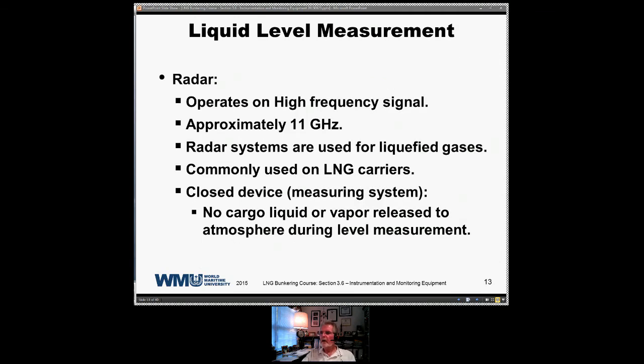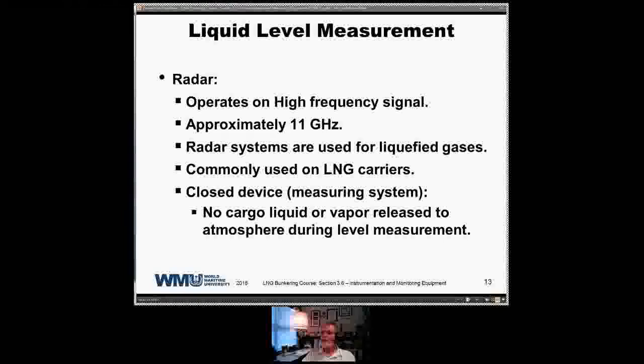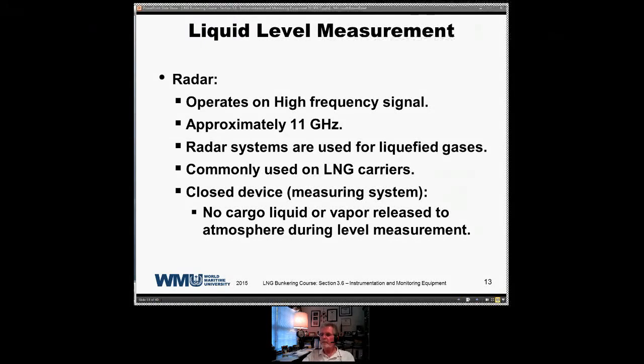Radar has been around for a long time. Now it's used to measure liquid levels on all sorts of liquid carriers. For LNG, it's a very, very popular means of measuring liquid depth inside a tank. It operates on a high frequency, 11 gigahertz, and it's obviously used for liquefied gases and commonly used on LNG carriers. It's a closed device, just like the capacitance probe. Everything takes place inside the tank. At no time does any vapor or any liquid come in contact with the outside environment. No liquid cargo is released during level measurement. And the level is monitored all the time.